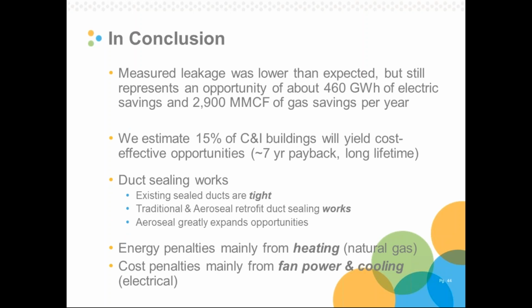So, in the end, we measured leakage. It was a lot lower than we expected, but there is still an immense opportunity. I mean, even looking at just the 15% of systems with high leakage, we're talking about 460 gigawatt hours a year of electric and 2,900 million cubic feet of gas savings opportunities a year. A lot of energy moves through commercial and institutional distribution systems. Even fixing a small amount of that is going to have massive savings.